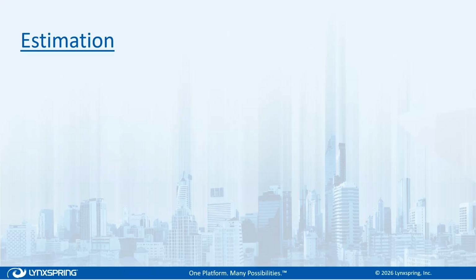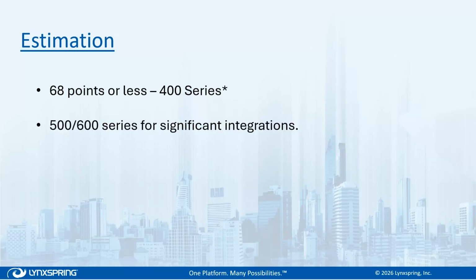If you have 68 points or less, I would recommend the 400 series. I really like the 400 series a lot, especially because it does have a lifetime SMA as well. But for just straight control, I would stick with the 400 series. Now, if you need some significant integrations, then the 500 and 600 series are where you want to go.